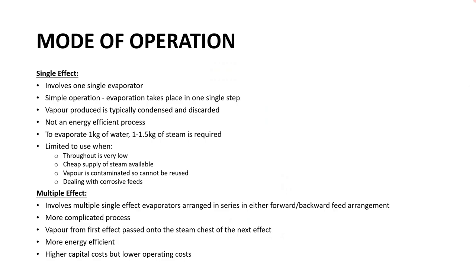There are a number of different modes of operation in an evaporator. The most simple is a single effect evaporator, where evaporation takes place in one single step using one evaporator. As a result the process is relatively simple; however, the vapour that is produced is then condensed and typically discarded, which is quite wasteful. Typically, to evaporate one kilogram of water using a single effect evaporator would require anywhere between 1 to 1.5 kilograms of steam, which is not very efficient.